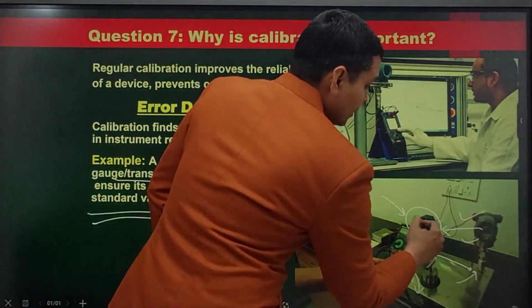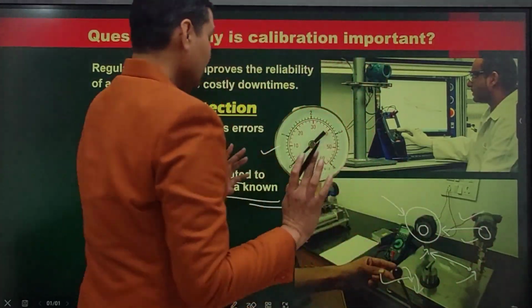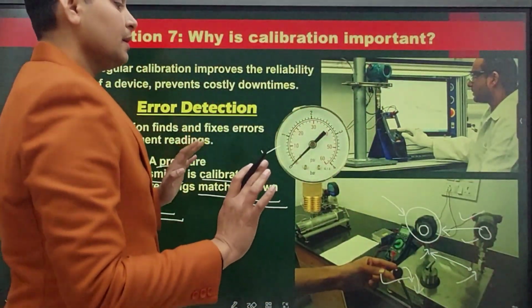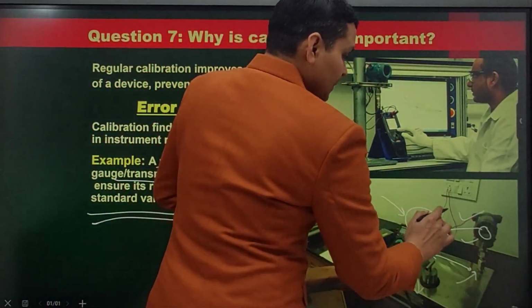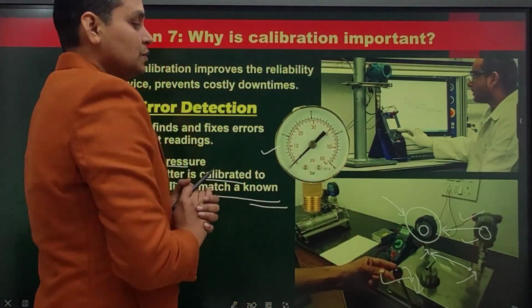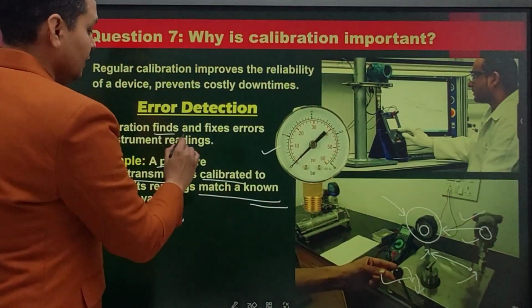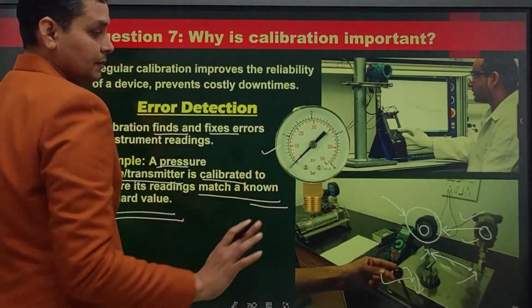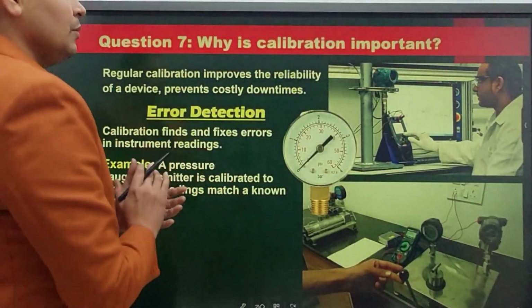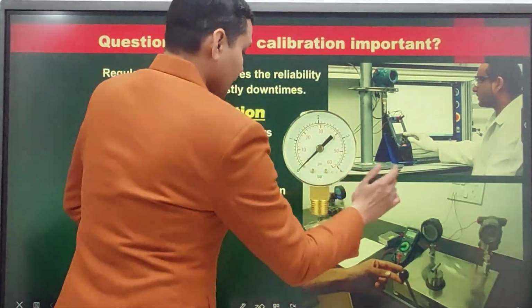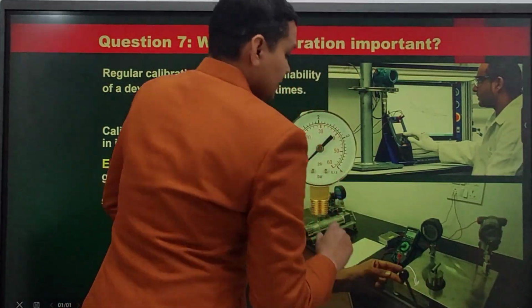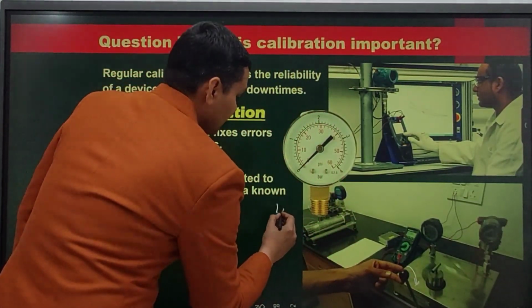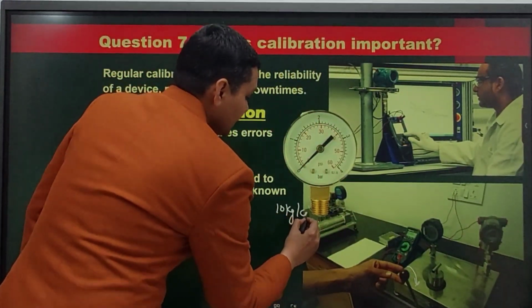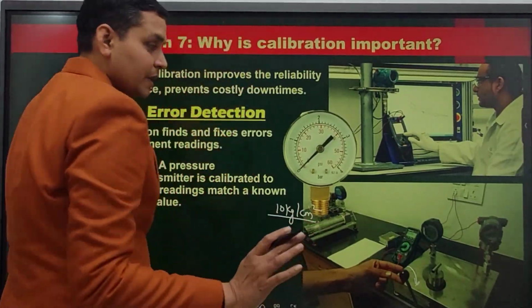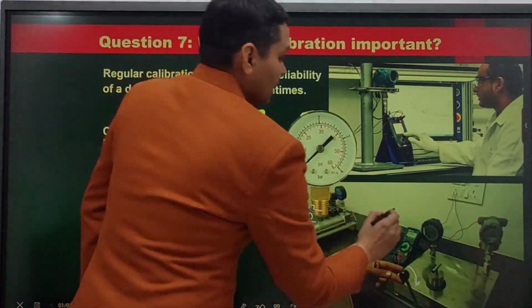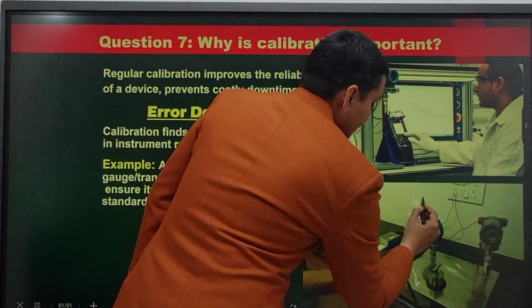If this value is also present here, then there will be no error. If there is any mismatch, then there will be an error. So we will find and fix the error. Suppose we are calibrating a pressure transmitter and by rotating this wheel, we are developing a pressure. Let's say it is 10 kg per centimeter square. So here it will be 10 kg per centimeter square.